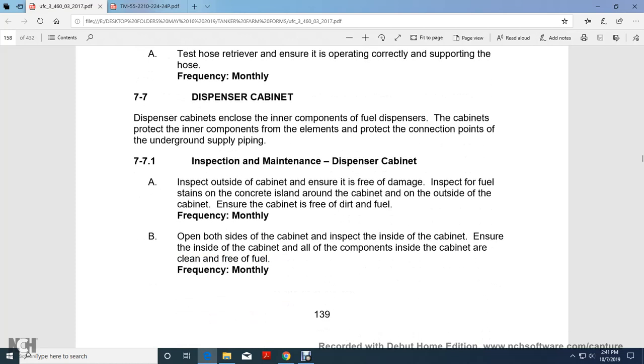Inspection of the dispenser cabinet. Inspect the outside of the cabinet. Ensure it is secure and free of damage. Inspect for fuel stains on the concrete island, inside the cabinet, and on the outside of the cabinet. Ensure the cabinet is free of dirt and fuel monthly.